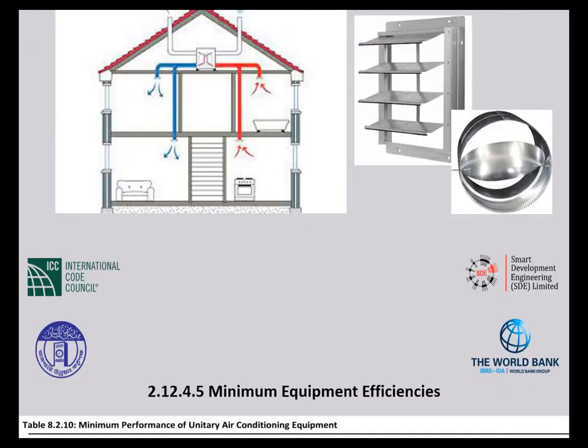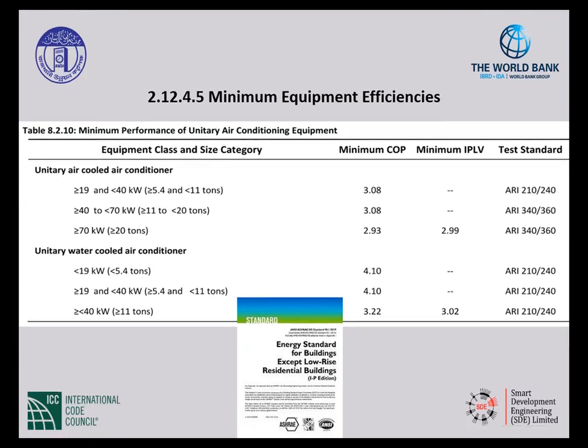All right. Efficiencies of our equipment, yes, we're always going to have minimum equipment efficiencies. The older equipment didn't run quite as efficiently as the newer equipment, so we have these tables in the code that tell us, depending on what kind of equipment, what kind of efficiency it has to be, what coefficient of performance or integrated part load value, lovely terms that we have to learn when we're doing mechanical systems. So what efficiency do we have, and according to what test standard? Then it says, okay, if you don't find your piece of equipment in here, then go to ASHRAE 90.1 to find what the efficiency of that equipment should be.